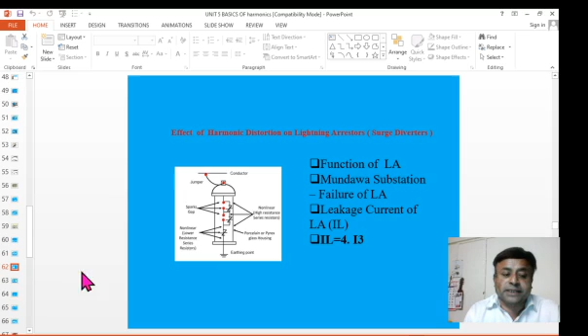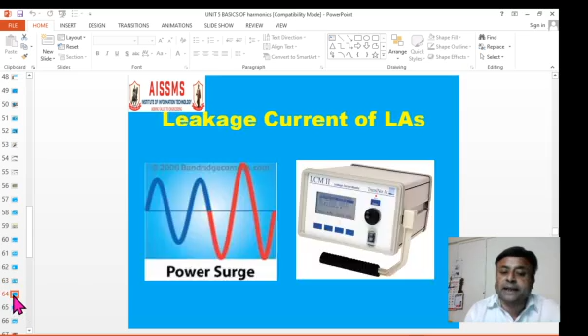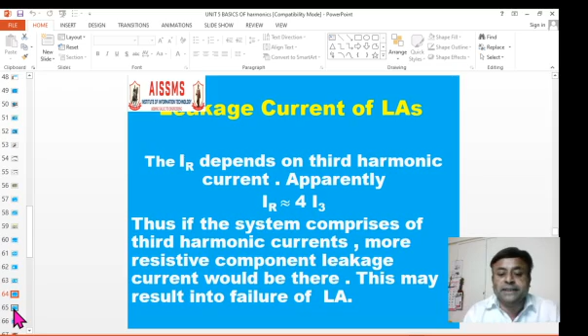As can be seen here, IL is 4 times I3, that is, the leakage current is 4 times the third harmonic current. Therefore it will record 4 times the third harmonic current, which is very high and sufficient to cause failure of the lightning arrestor. This was seen through the leakage current measurement unit, LCM, and it was revealed that the harmonics are more. So IR equal to 4 times I3 is the important equation, which is the basis for finding out leakage current, giving an empirical relationship between third harmonic and leakage current.